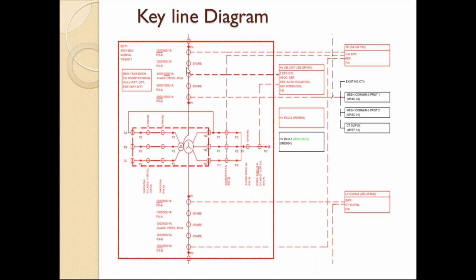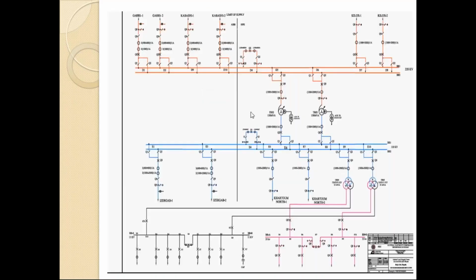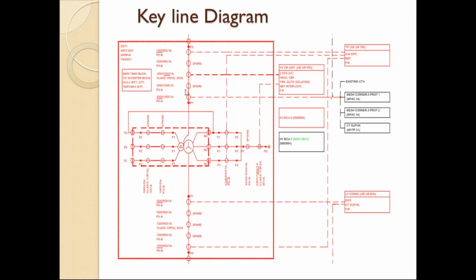So each CT is having different protections, because the first CT goes for the transformer protection, and the last CT is towards the bus. Above this transformer, if you see, there are some buses connected, a bus bar. So this CT will be protecting towards the bus, and this one is used for the CB unit.